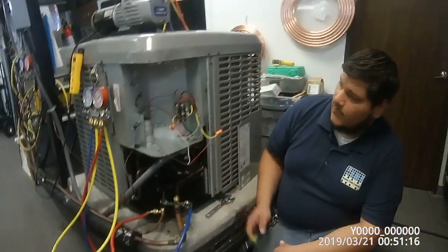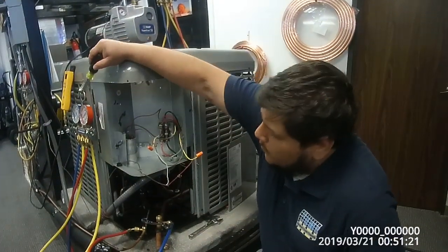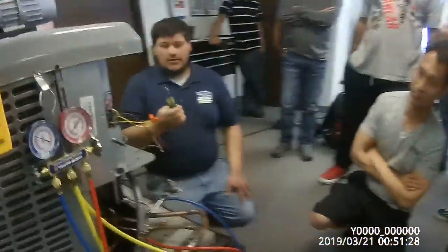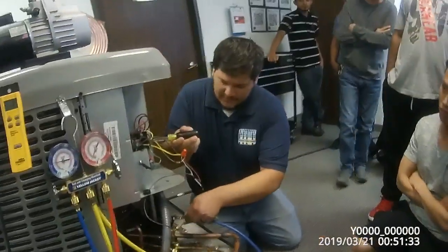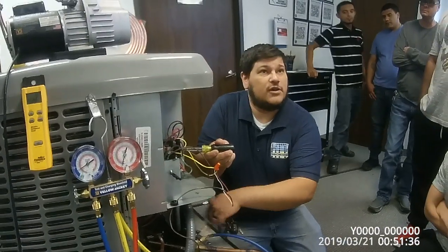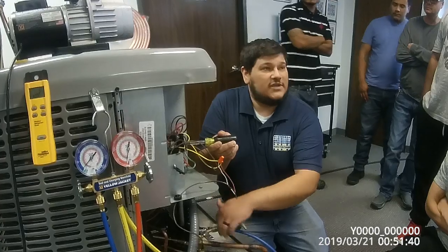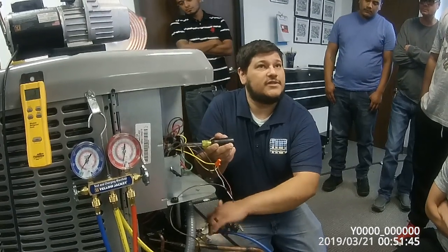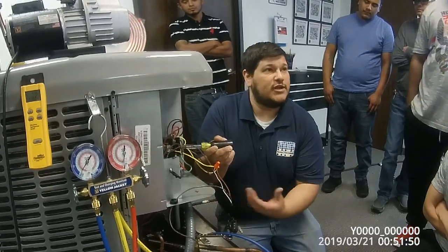Now what we're going to do is engage the contactor. Watch my pressure — make sure it goes all the way down to zero. Hold your insulation, engage your contactor, put this over to my low side. I'm steadily going to start closing my low side as I go, because you don't want to overdo this. Once it's at zero, there's no more refrigerant — that compressor is just struggling. You got to hurry and close it. But don't let off your contactor until this valve is closed, or the compressor will shoot back.